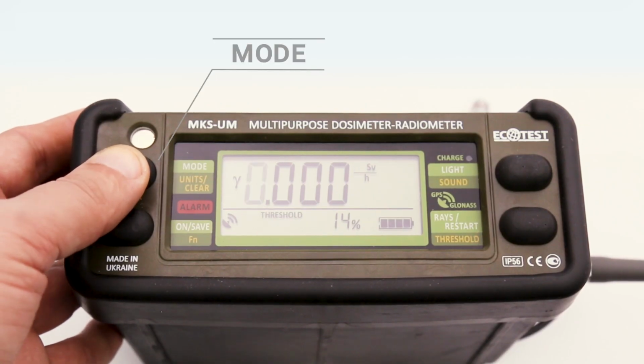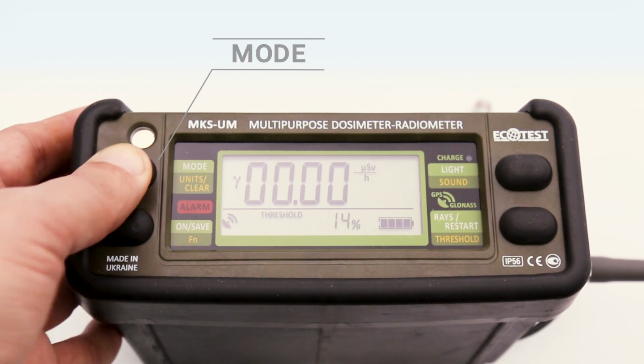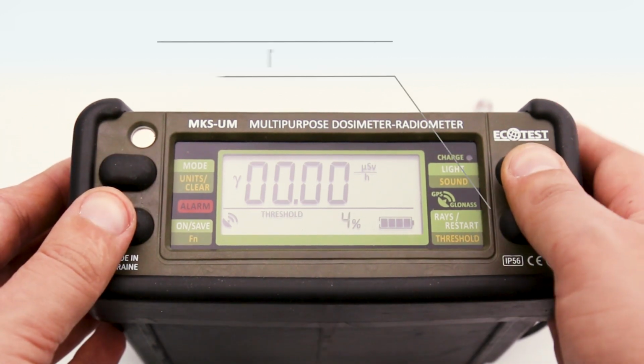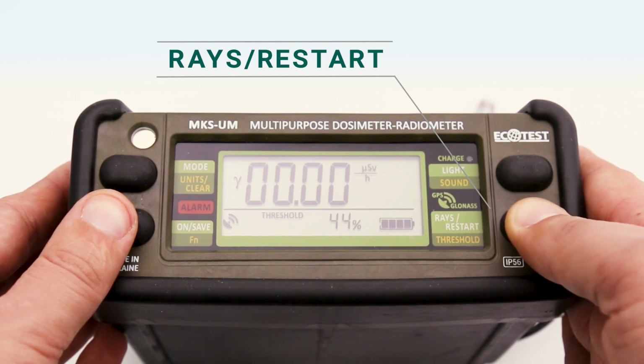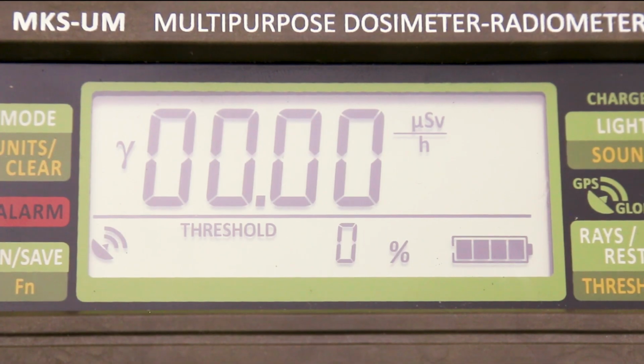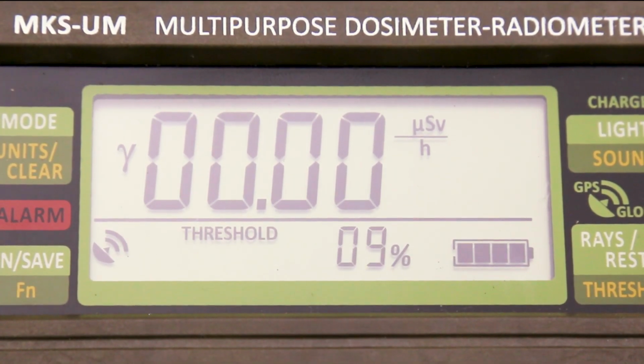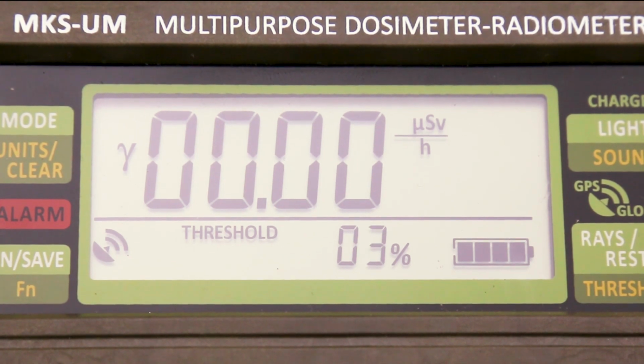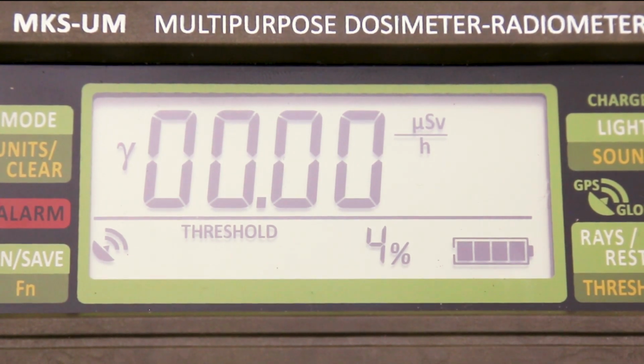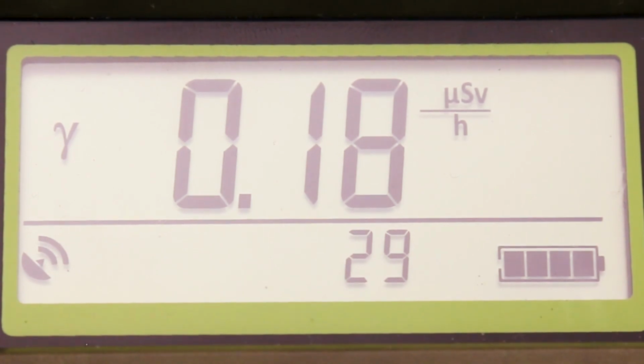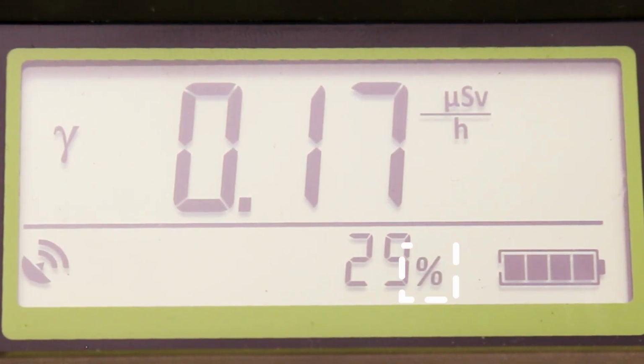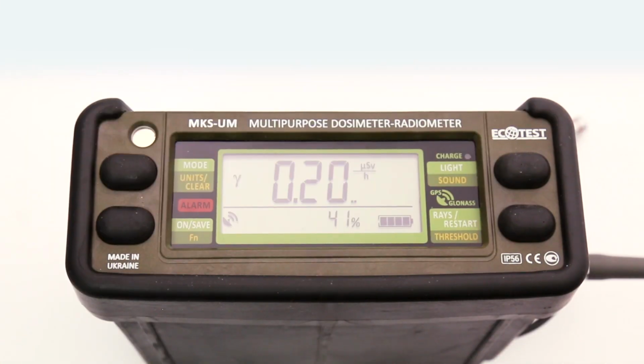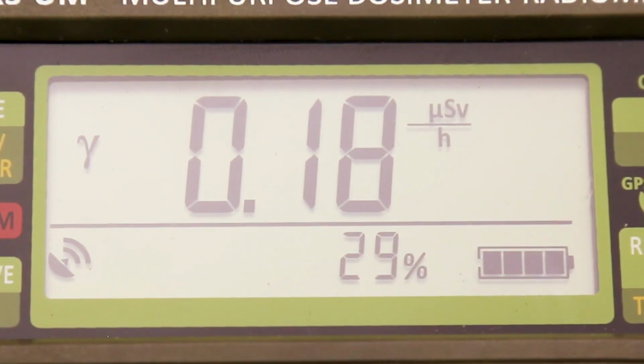The dose rate is measured by the device before obtaining the results with a programmed statistical error, which, depending on the radiation intensity, can be determined by the device or set by the user in a submode of threshold levels programming. In the latter case, a flashing % symbol appears. You can view a threshold level value and a programmed statistical error in the mode of displaying the measurement results.